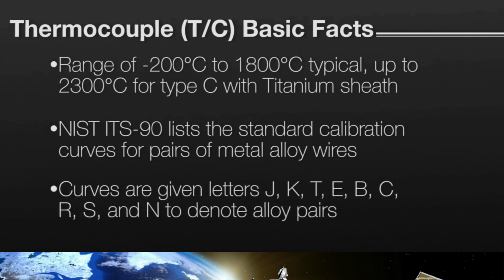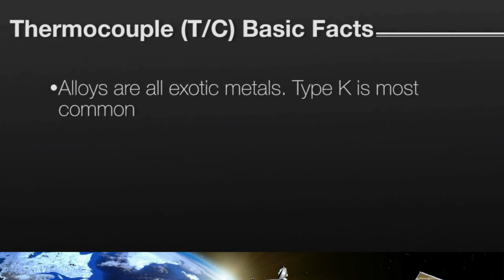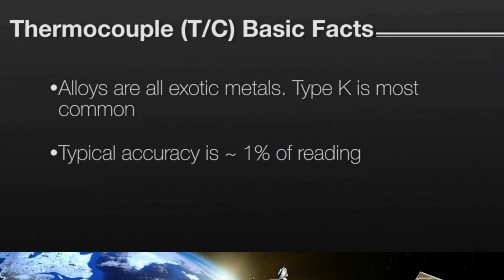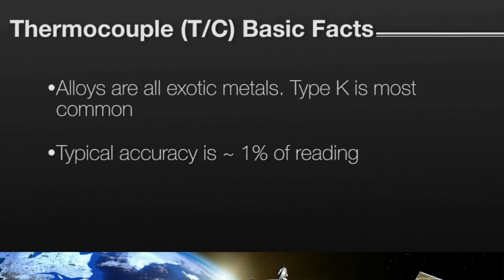Alloy pairs are given letters of the English alphabet, types J, K, T, and so on. I have no clue why those letters were used, as they don't correlate to the names of the alloys or the metals inside them. Type K is the most popular one in use because of its broad temperature range and its low cost. Typical accuracy is 1% of reading. To do better than this, you'd have to ask your supplier to individually calibrate each thermocouple probe they sell you.